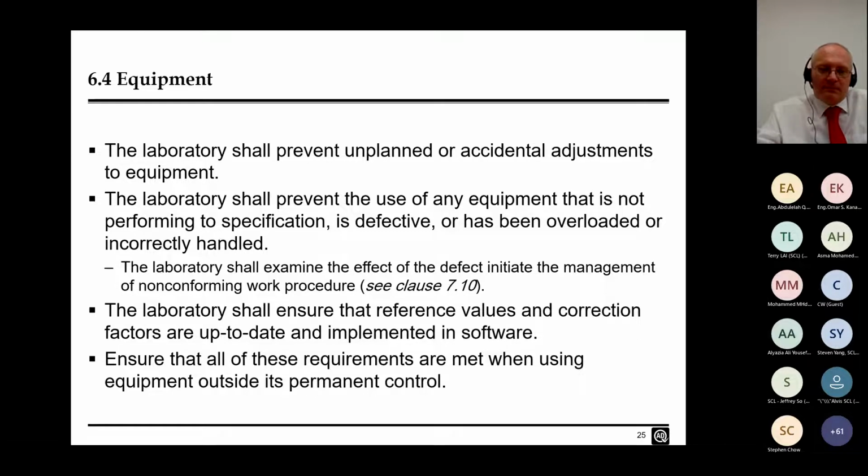It's really important. There's nothing worse than someone dropping something, putting it back on the shelf, and you use it for some months, and then you realize that something's happened to it and the value's been wrong. And then you have to go back to your customers and withdraw your certificates, and you have to fix these issues. It's much better to know on the day. And as a head of lab, I try not to get cross with people who have dropped or broken my equipment.